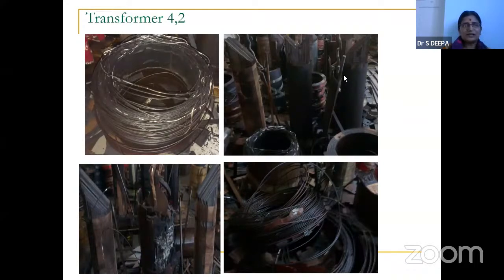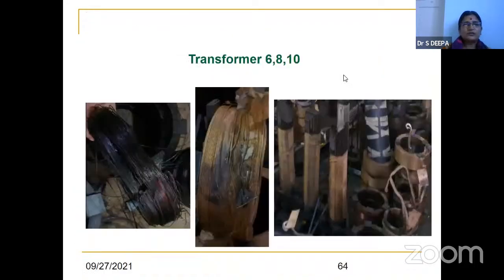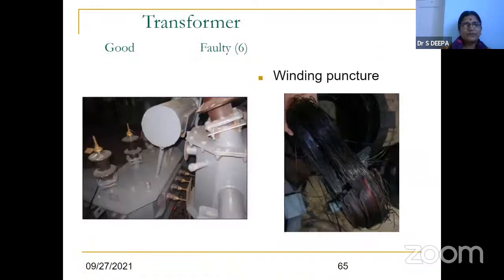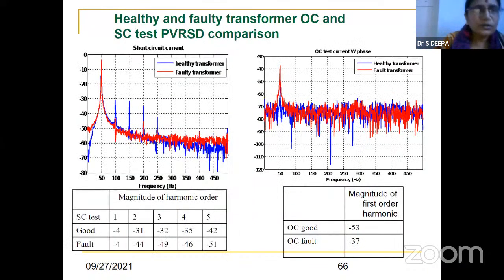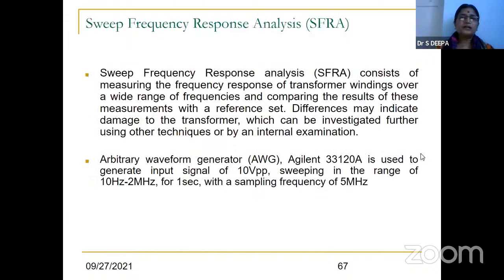What are the faults that are occurring? I took these photos of the different faults. So punctured. So what to do is, first without the fault and with the fault, after rewinding, we have to take up the faulty transformer and the healthy transformer, OC and SC tests. Okay, open circuit and short circuit tests. So that is what we had seen.